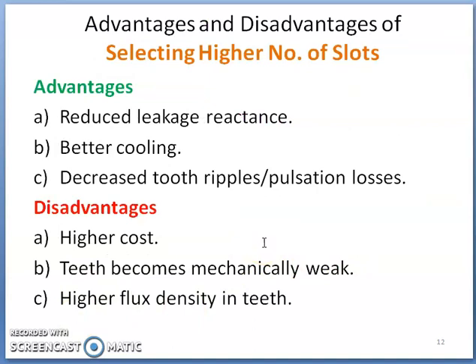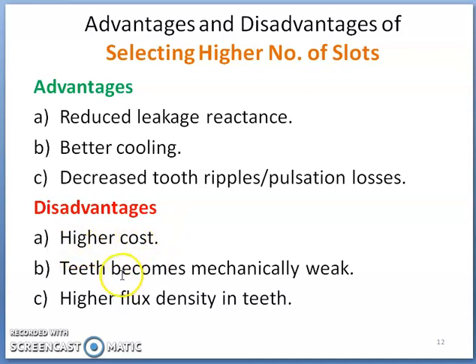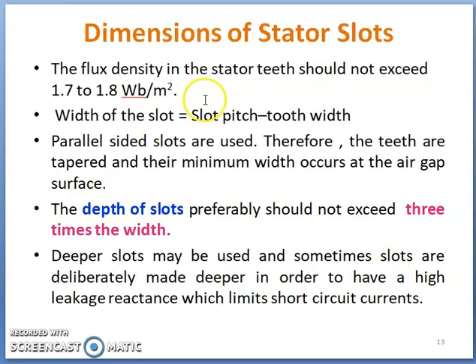The advantages of selecting a higher number of stator slots include: reduction in leakage reactance, better cooling because conductors per slot are fewer, and reduced tooth ripples as well as pulsation losses. The disadvantages include higher labor cost to insulate, place, and tape conductors, and the teeth become mechanically weak due to the decreased teeth section, while flux density in the teeth increases. Based on these trade-offs, the designer decides the optimum number of stator slots for the given machine.